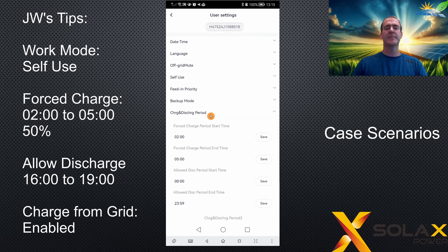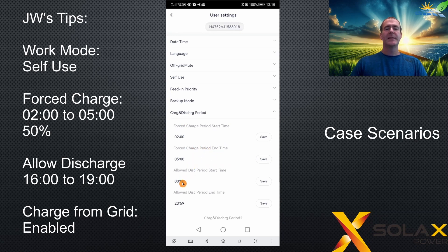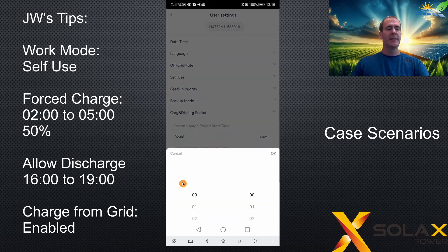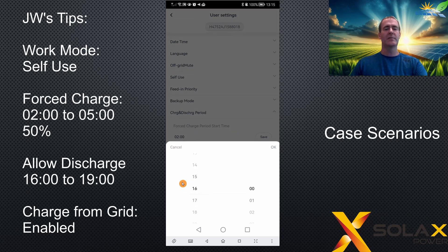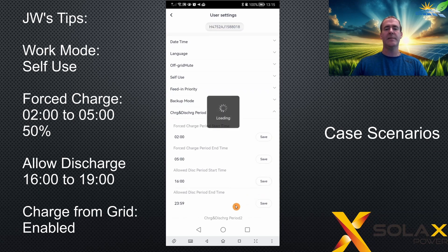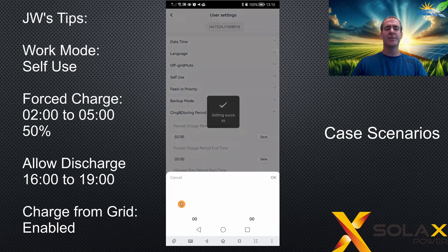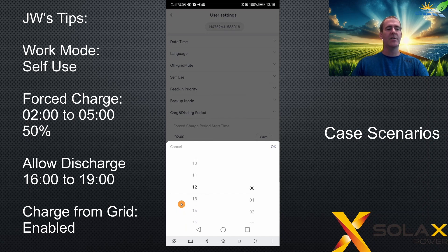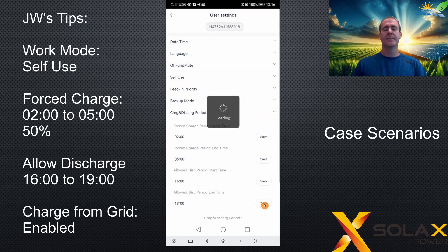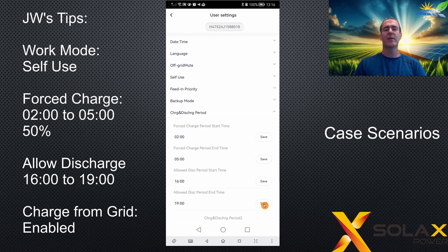Move down to the charge and discharge periods. We're going to force charge to 50% between 2 o'clock and 5 o'clock, so set 2 o'clock for your start time and 5 o'clock for your end time. This time we're going to change the discharge period to save your battery until the peak times — pick 4 o'clock for the start time and click save. Set the end time to 7 o'clock and click save. That's now set up to charge up to 50% from 2 to 5 in the morning and only discharge the battery to house loads between 4 o'clock and 7 o'clock in the afternoon.